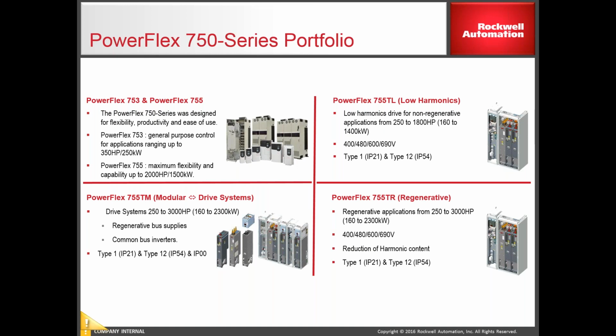And then we have the TM, which is a modular drive system, where we have an active front end, we have a bus supply, we create a common DC bus, and depending on the requirements of the application, you can start hanging inverters off of that DC bus to run a system. So for example, on a paper machine where you've got a wet end section where you might have 5 or 6 drives you need to run in a group, you can hang all those inverters off that one common DC bus.